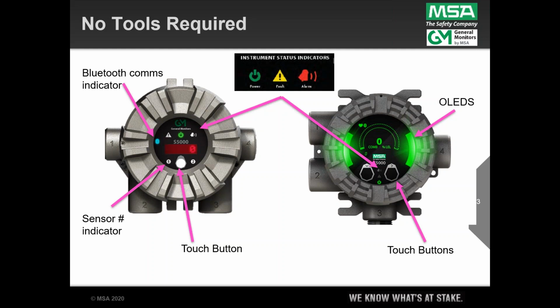And then the X5000, right, that's got these really bright organic LEDs. So if it's a benefit to any customer to have a super bright LED, man, that when it turns red, you can see this sucker a long ways away. That's a benefit of that guy. Now on the S5000 on the left, the housing is a little different because our designers wanted to make it easy for a customer with legacy General Monitors gas detectors to be able to use the same footprint with this guy. So he's a much easier upgrade if there's existing infrastructure on site with our legacy gas detectors. The S5000 supports that same mounting footprint.